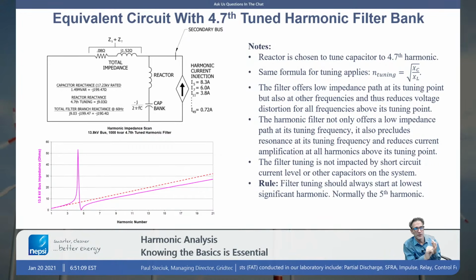Number 2 is you want to avoid resonance. You're installing reactive compensation on a network, but I'm trying to avoid resonance. How do I avoid resonance? I put a filter in, or I detune the capacitor bank. Sometimes you talk about these as detuned cap banks. And then the third reason is you want to actually do filtering, and this is also a requirement in a lot of the major projects, like mine projects, where you have very large non-linear loads.